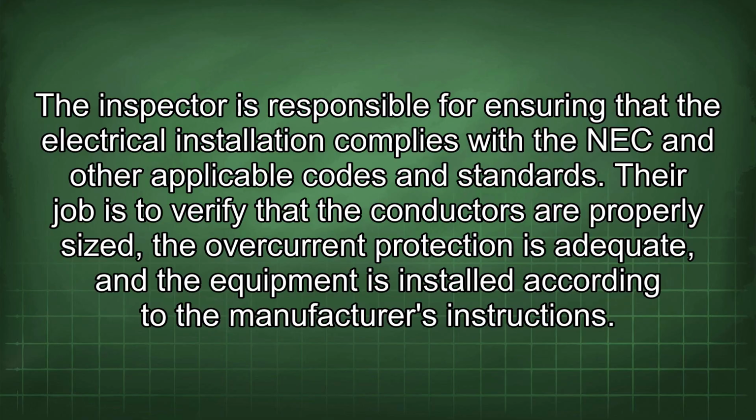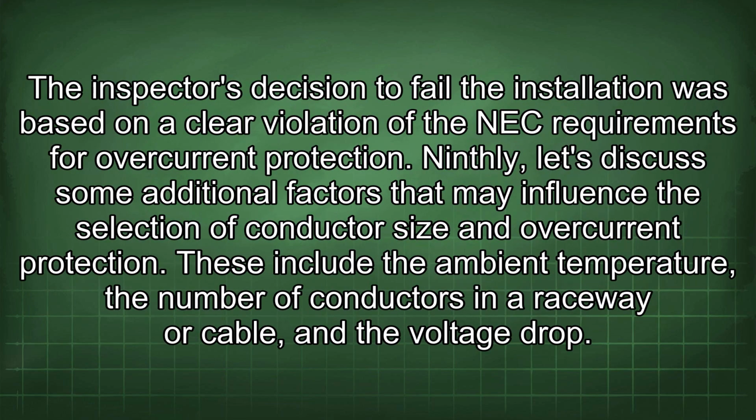Their job is to verify that the conductors are properly sized, the overcurrent protection is adequate, and the equipment is installed according to the manufacturer's instructions. The inspector's decision to fail the installation was based on a clear violation of the NEC requirements for overcurrent protection.